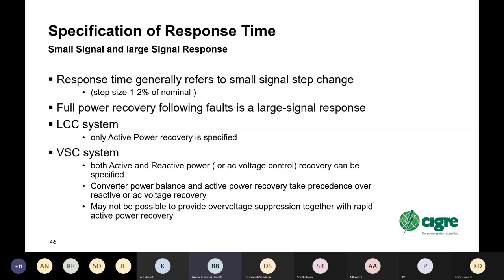Specification of response time. Response time really includes both small signal and large signal response. The small signal is typically the step response of the controller to a step input. It generally refers to a small signal change, 1 to 2% of nominal, whereas full power recovery following faults is a large signal response. With an LCC system, only active power recovery is specified. With a VSC system, both active and reactive power recovery can be specified.